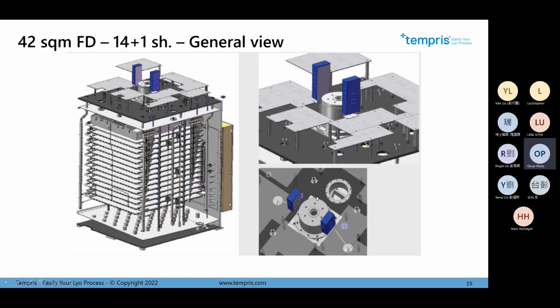Here, for example, is a study of a large freeze dryer, 14 shelves. We place two systems, and we place antennas in different sites, depending on where we want to measure in this freeze dryer, which is also very important. What are the requirements from the customer, or where do we want to measure? And the more points we want to measure, of course, the more antennas we need. So we have to balance the system configuration by the requirements in order to get the best solution. Here we install the units very near the hydraulic system for the shelf moving.